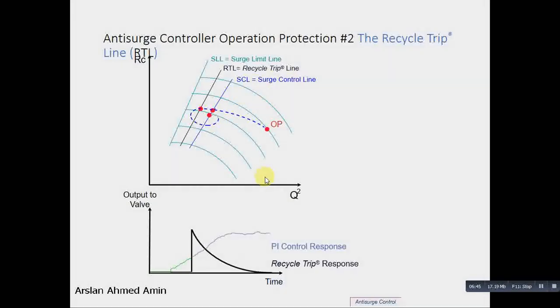When the operating point comes back to the surge control line, the recycle trip response diminishes like an exponential decay. This is an exponential decay response. The total response would be the sum of this and this. This is how the advanced antisurge control algorithm works.